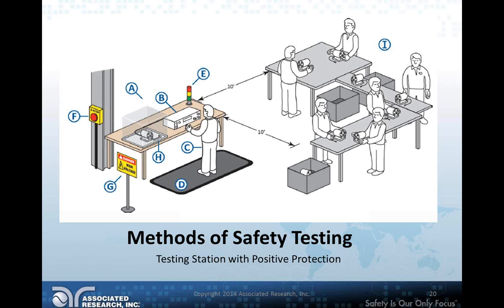A couple other things of note in here. C is the operator him or herself. D is an insulation mat, which you can put on the floor. Insulation mats are another good way to isolate an operator from ground potential. Because as we mentioned, ground potential could give you a low resistance path to ground, but if you insulate yourself from that, you're just mitigating the shock hazard. You'll also see E there is a safety light. Basically, that light would be illuminated red when your hipot station is in a ready state. You'll also notice G, or let's go with G first. I skipped a letter, but it is basically a danger high voltage sign.